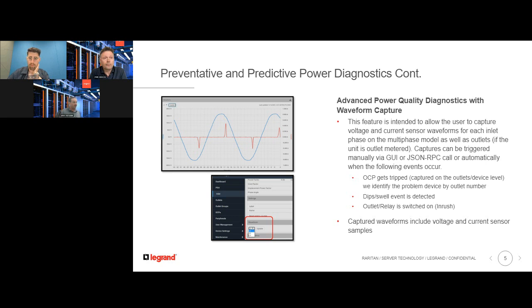But what's interesting, and it gets back to, I think, something Sven alluded to earlier, and kind of an old thing from the Green Grid, was you really can improve what you're monitoring, and whether that's power or power quality, or understanding if you've got a power problem, by capturing the waveform here, which is current and voltage. We can give you that type of data. What's amazing about it, it's continuous and real time. So if you suspect you have problems, you don't need to go out and purchase a separate meter or do anything like that. We can give you that data instantly. And if you want to look at, say, the waveform at the in-feed of the PDU, you can manually capture that as well. And then, of course, this information is available on the GUI or as part of the API.